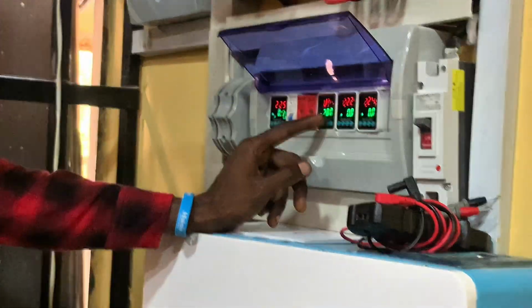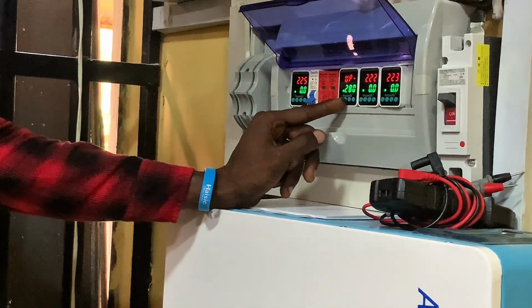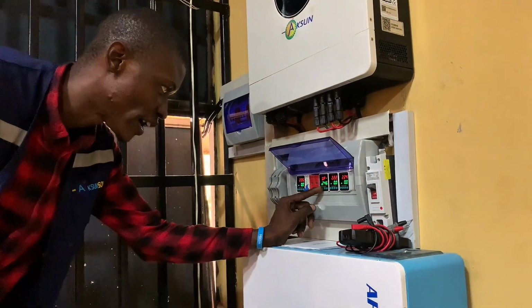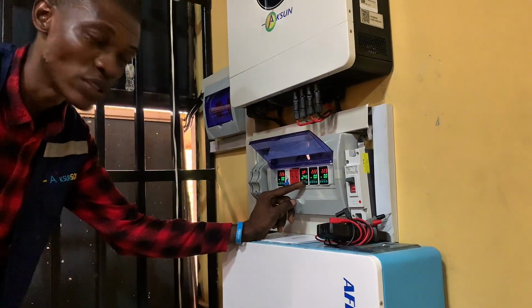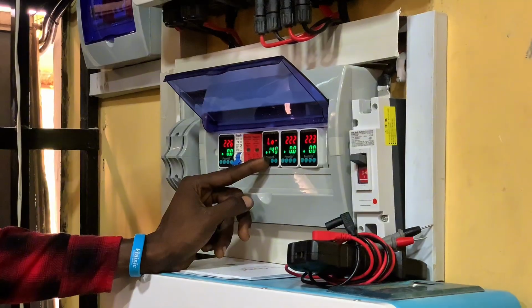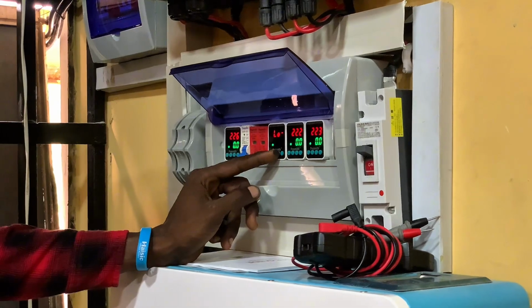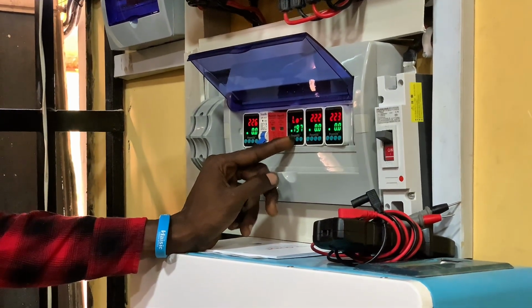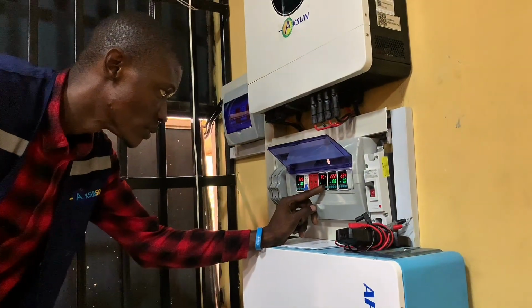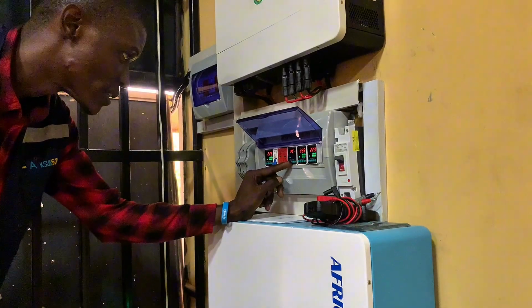So now we have our menu here, we just press menu. The first setting is over voltage. I like using 245 for my over voltage, which means if it senses any voltage higher than 245, it cuts off. The next is under voltage, I like using 185, which means if it senses anything lower than 185, it cuts off. We have our current, remember we said we're using 14 here, so I'll bring it down to 14.